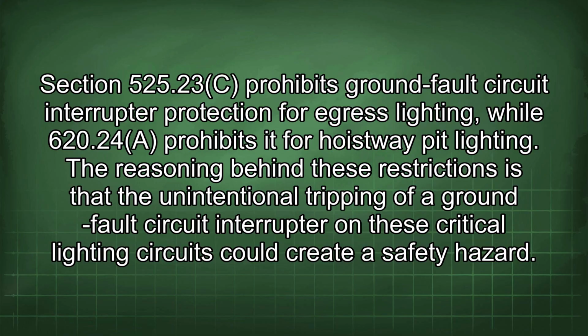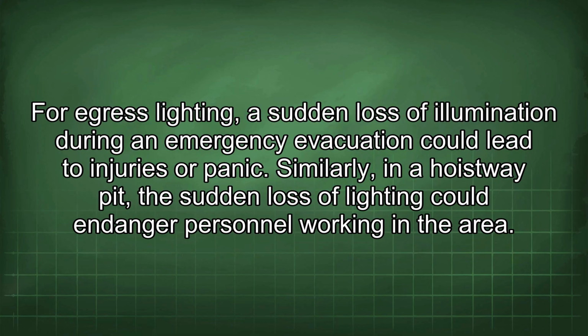The reasoning behind these restrictions is that the unintentional tripping of a ground fault circuit interrupter on these critical lighting circuits could create a safety hazard. For egress lighting, a sudden loss of illumination during an emergency evacuation could lead to injuries or panic. Similarly, in a hoistway pit, the sudden loss of lighting could endanger personnel working in the area.